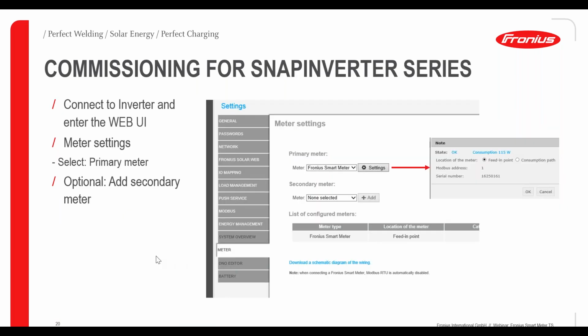Regarding the Snap inverters, to get into the web interface, you activate the Wi-Fi access point via the display of the inverter. Then you enter the same IP address as I mentioned to get into the web interface of the inverter. Once in the web interface, under Settings and the sub-menu Meter, you can add the primary smart meter. So you add the Fronius smart meter here, then you receive messages in the box, and you choose the positioning of the smart meter. You can choose either the consumption path or the feeding point. In this case, it is the feeding point.